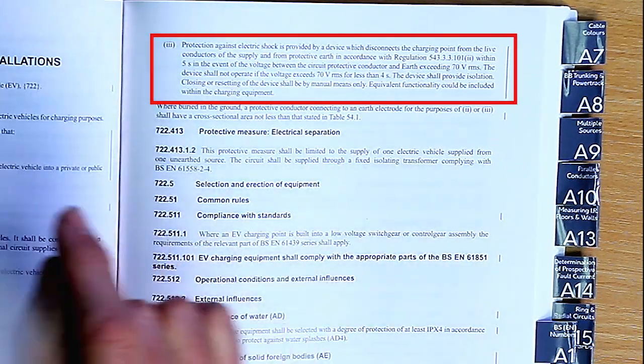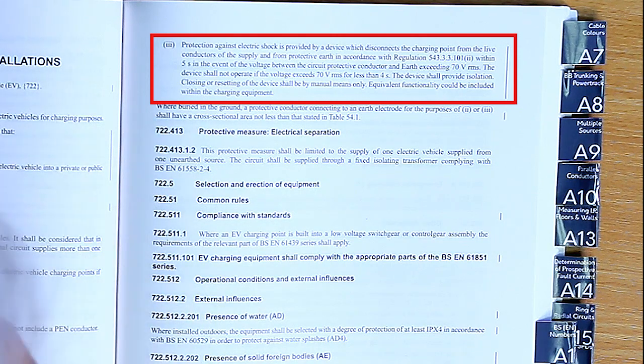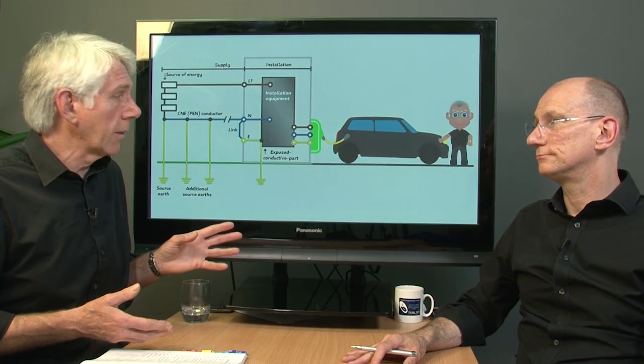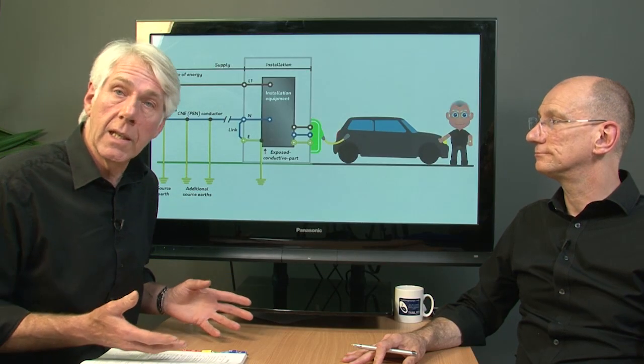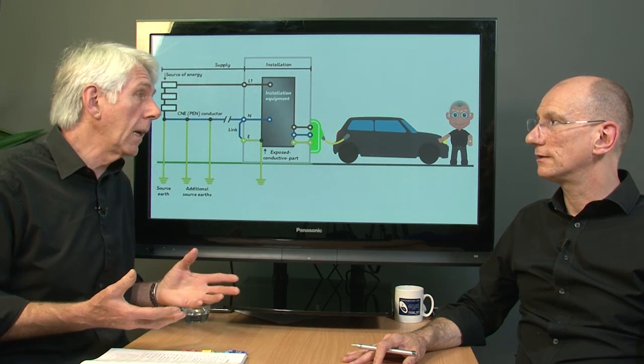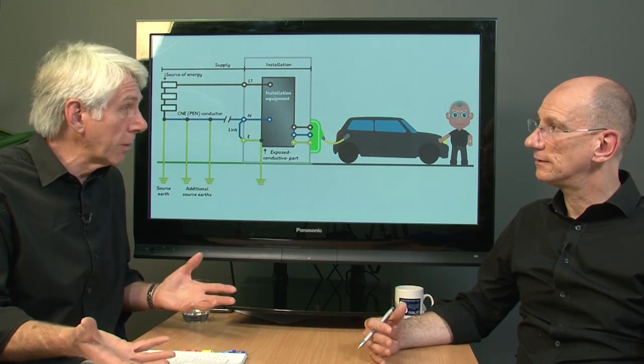Protection against electric shock is provided by a device which disconnects the charging point from the live conductors of the supply and from protective earth in accordance with regulation 543.3.3, and it goes on a bit. Now, until recently we were saying no such device exists, but in fact they are now starting to appear in various forms, sometimes involved with the charging mechanism itself.